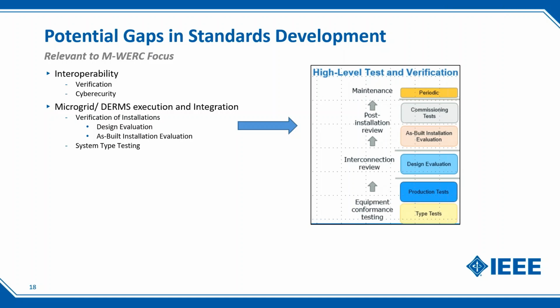In North Carolina, two years ago, there was a survey of 51 megawatt solar PV systems, and 40% of them had the wrong inverter settings, even though it was in the contract. Another 30% of those had the wrong grounding configuration. So there need to be checks on the systems being installed, to see if they're actually what's required by the contractor, by the region. Another step is an as-built installation evaluation.